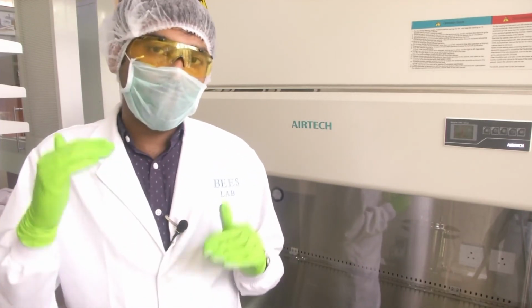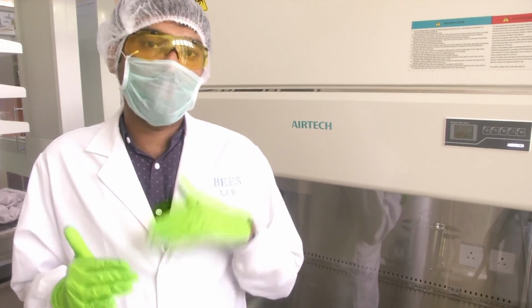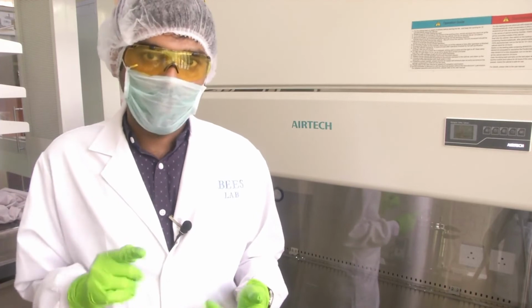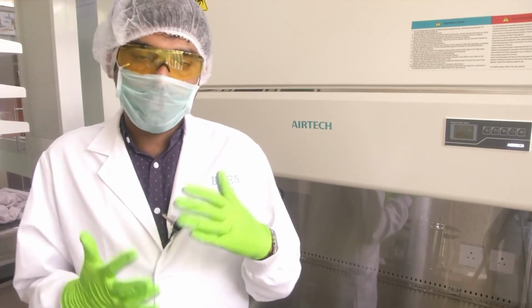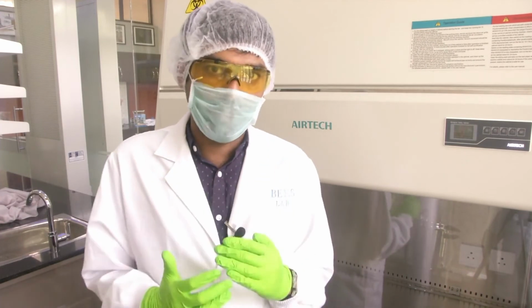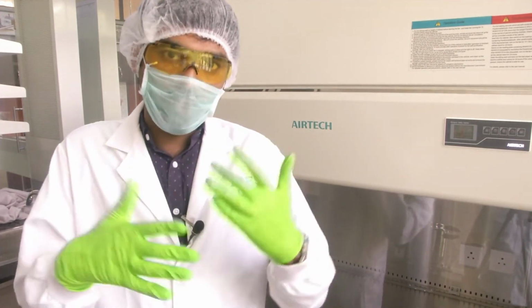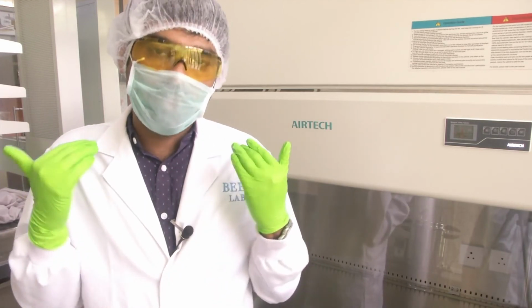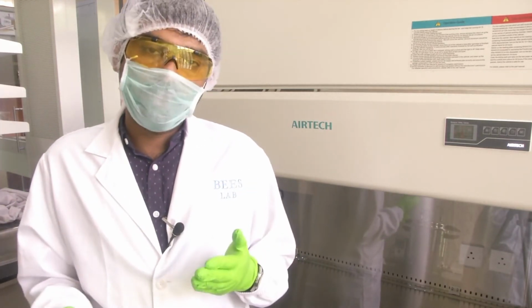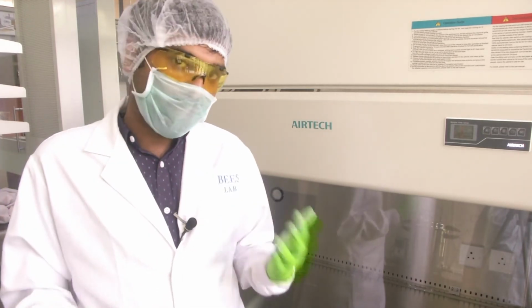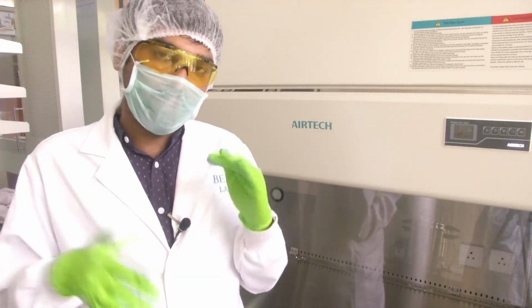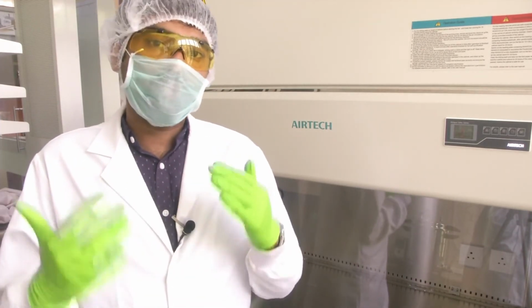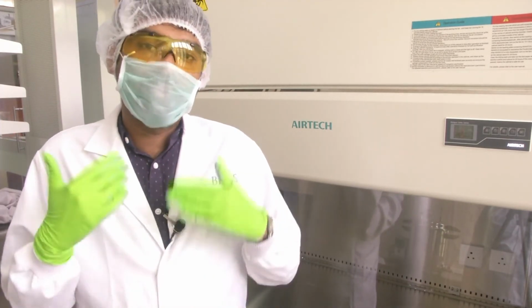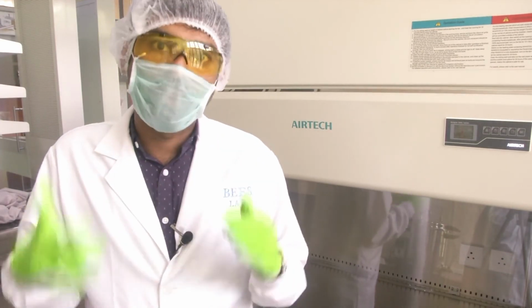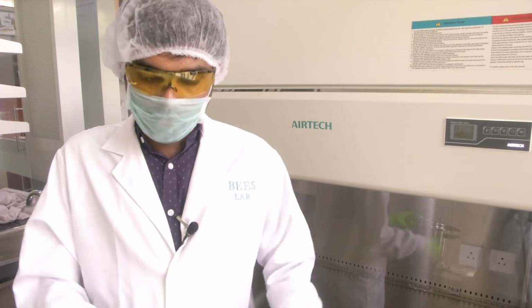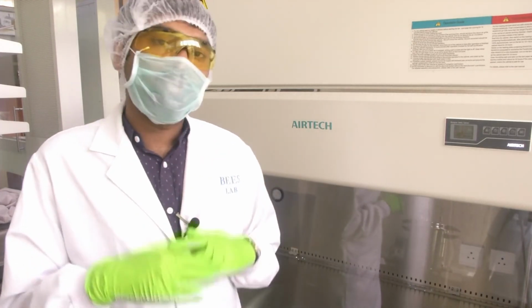So, when your biosafety cabinet has provision to circulate HEPA filtered air, and also the chemicals that come out while your sample interacts with the chemicals that you add, the vapors, these vapors will also be HEPA filtered before they enter the environment. This way it provides environmental protection and personal protection, and because we are using HEPA filtered, very clean air to circulate around the sample, the sample is also protected from unwanted changes. Thereby we get product protection. So, product protection, personal protection and environmental protection. This is class 2.